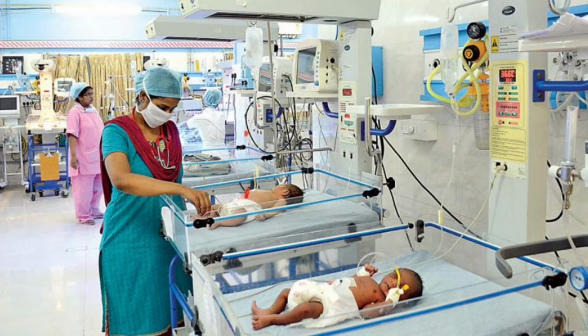The ambient temperature in labor ward, theatre, and the nursery can be carefully regulated. Any delivery suite, including in the emergency department, needs to have a radiant warmer in preparation for newborns. The radiant warmer has a small bed with safety sides. It has heating above the baby, oxygen, monitors, including temperature monitoring of the infant.